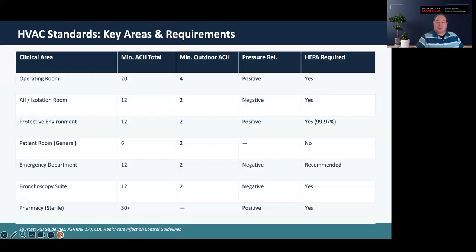Another relevant example is a bronchoscopy suite, because if you're doing sputum collection, you can have aerosolization. That's why it's treated much like an isolation room or protective environment, with a minimum air exchange of 12 and a minimum outdoor air exchange of 2, under negative pressure. Keep in mind bronchoscopy may sometimes be done in traditional operating rooms, where you'd have more air exchanges.